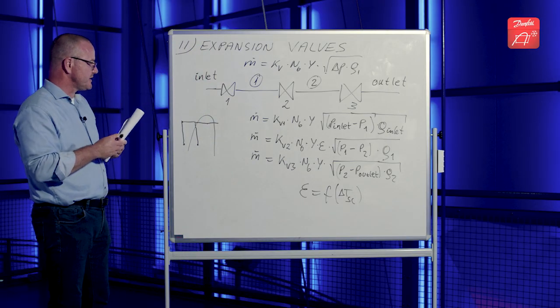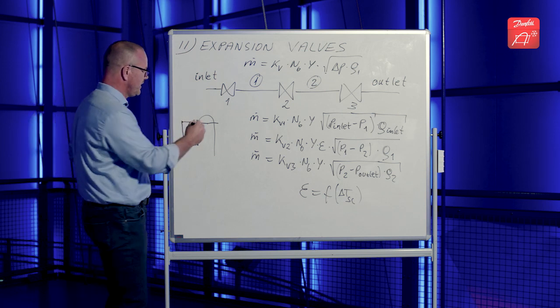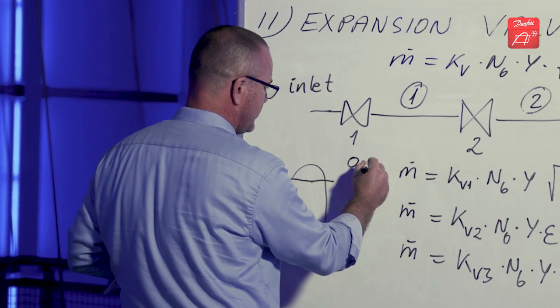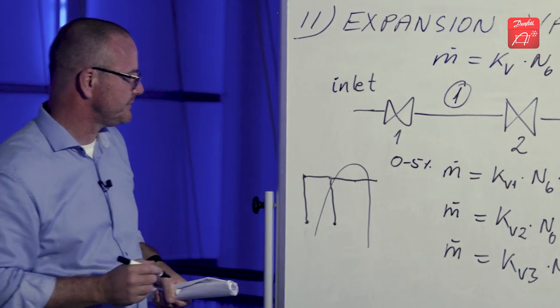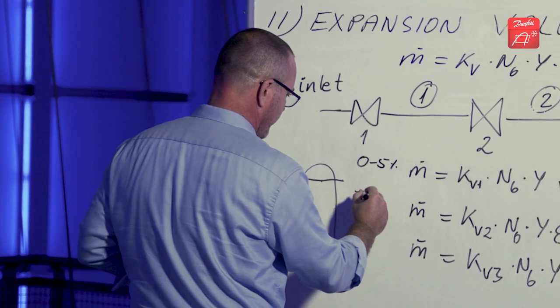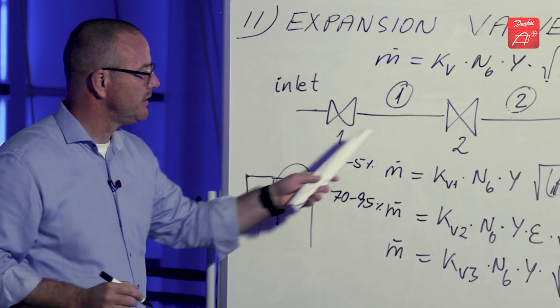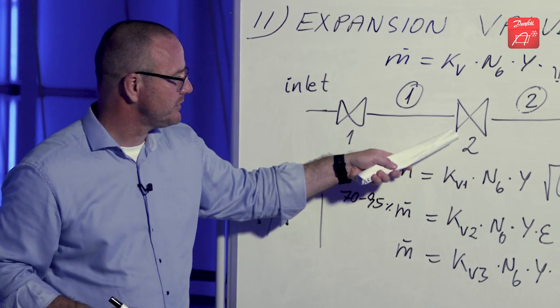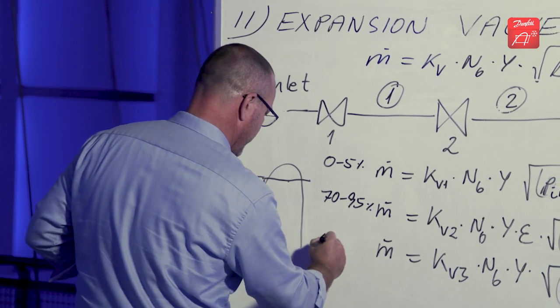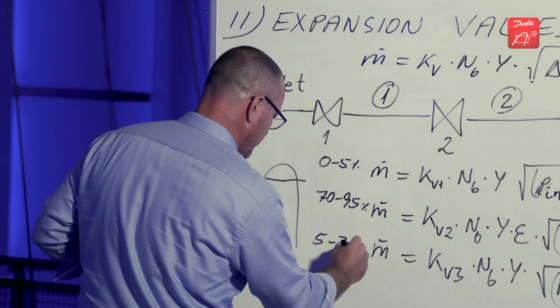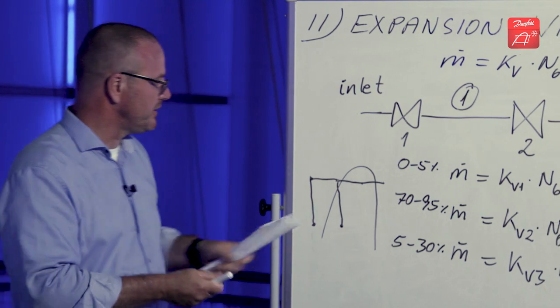Now, when you look at these equations, normally the pressure drop distribution is so that about 0-5% is on the first, the inlet valve. Then you have from 70 to 95% on the valve number 2, the main valve. And on the outlet, you have in the area of 5 to 30% of the pressure drop. So, that is approximately the distribution.